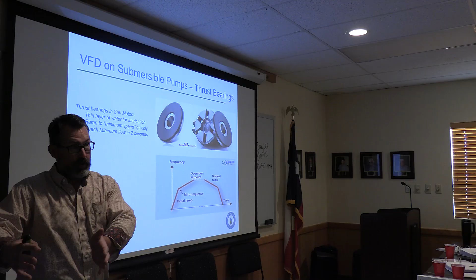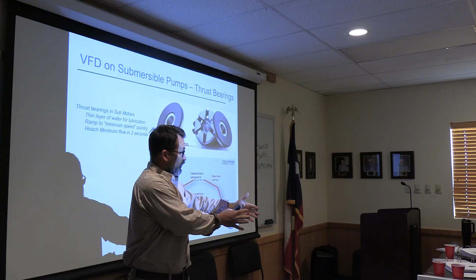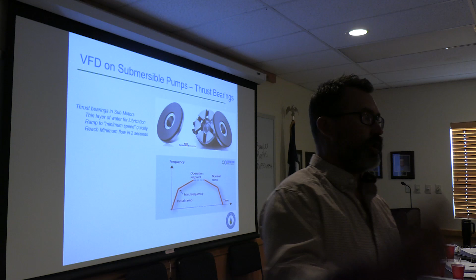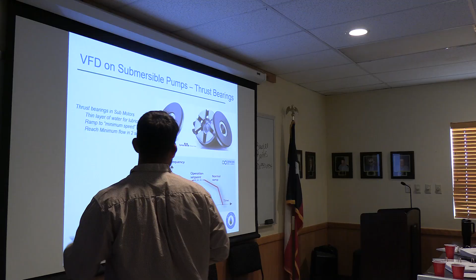So this is a little bit of a challenge here. I don't want an inrush, so I need to start this thing slowly enough, but I need to get to my flow in time so that I can functionally have a thrust bearing. And so you're working with some very sophisticated controls to say, here's my start, here's my full throw. I'm doing all of this within this weird 2-second window. So just a caution.